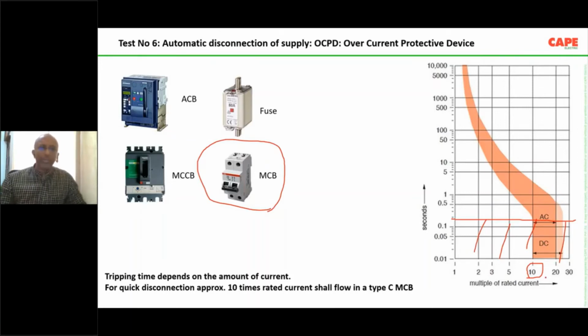What I wanted to tell you is the disconnection time of a protective device is highly important in electrical safety. What it means is you have a device to trip, and that particular device is supposed to trip within a specific time, not after a few seconds or after a few minutes. That is illegal. So it is supposed to trip within this particular time in case of a fault.